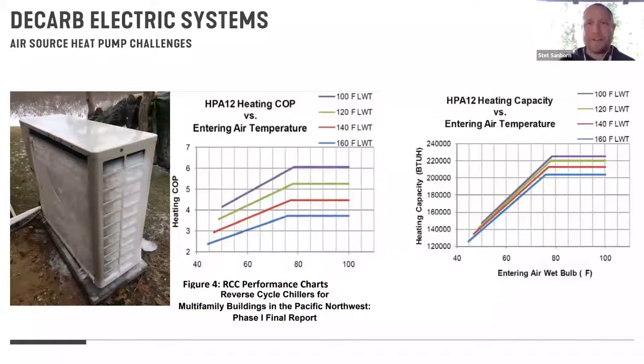And so oftentimes when we're looking at cost, trying to combine two systems, if we just said, oh, I'm going to buy an off-the-shelf air source heat pump and use that for space cooling or domestic hot water production, I'm going to end up buying way more than I really want to from a cost standpoint. And it certainly isn't going to compare advantageously to a gas-fired boiler or water heater. And so the strategies that we need to bring to bear for cold climates are really addressing these two factors. It's the coefficient of performance. How can we increase that? And how can we simultaneously increase the production of that piece of equipment so that it's not going to suffer as much during those cold days?